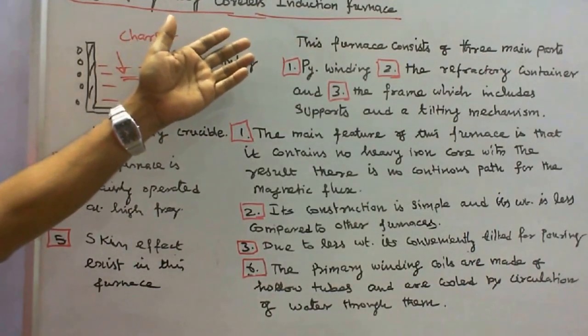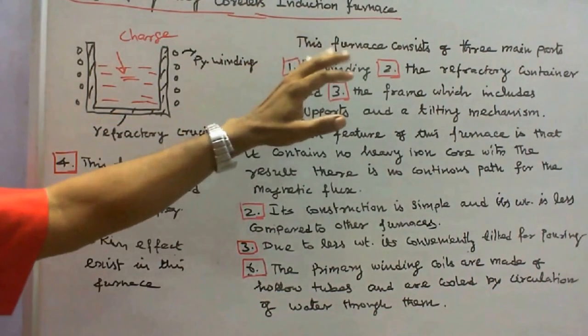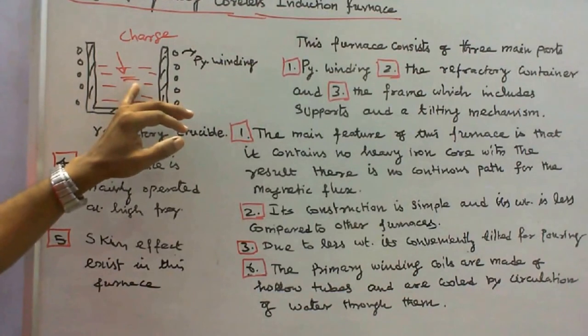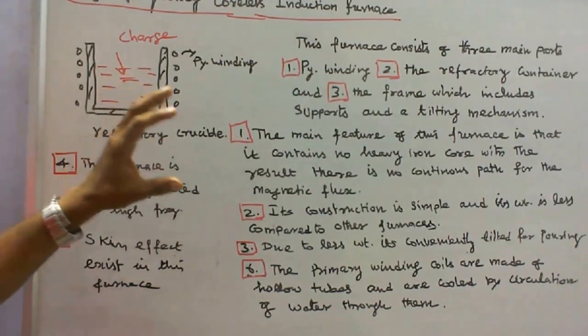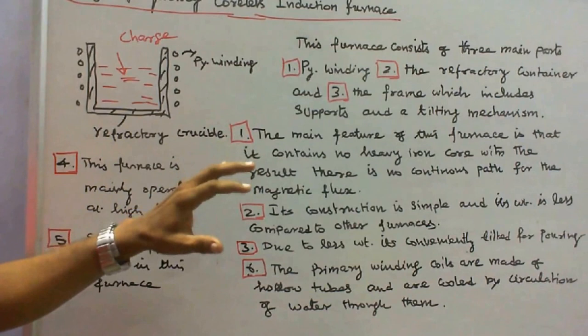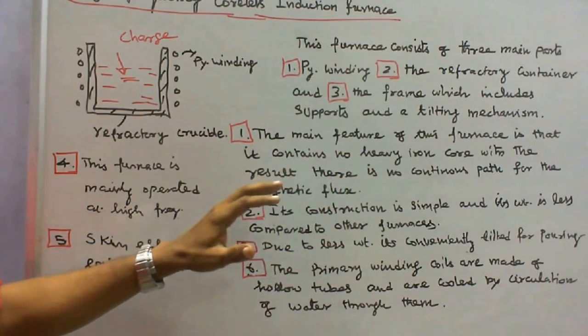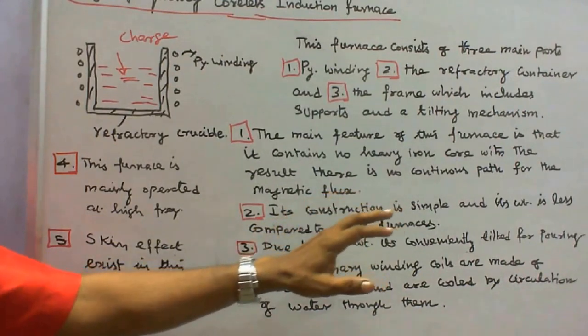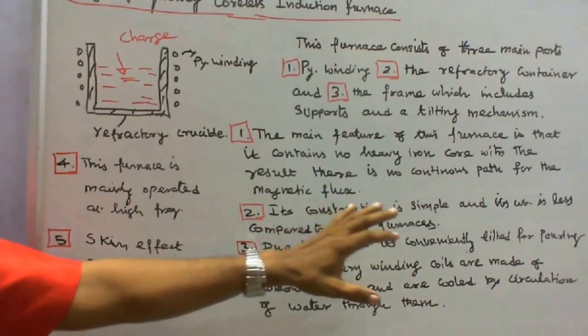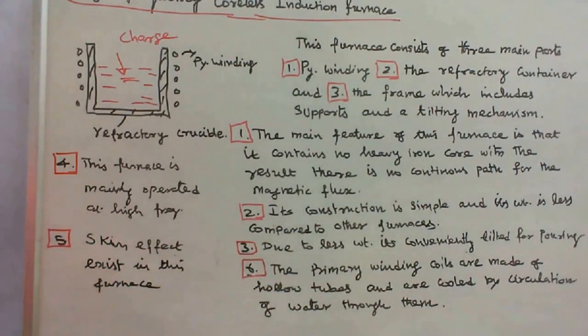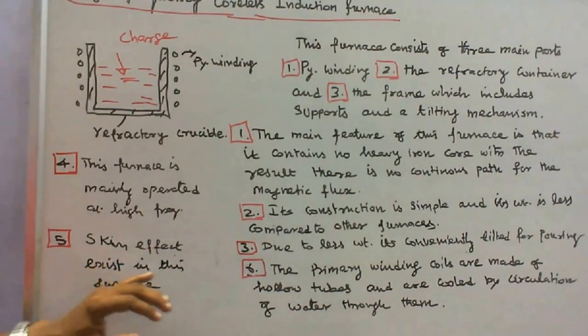The High-Frequency Coreless Induction Furnace consists of three main parts: one is the primary winding, two is the refractory container, and three is the frame which includes supports and tilting mechanism. The main feature of this furnace is that it contains no heavy iron core, and as a result, there is no continuous path for the magnetic flux. Its construction is simple and its weight is less compared to other furnaces. Due to less weight, it can be conveniently tilted for pouring. This furnace is mainly operated at high frequency, and naturally, the skin effect exists in this furnace.